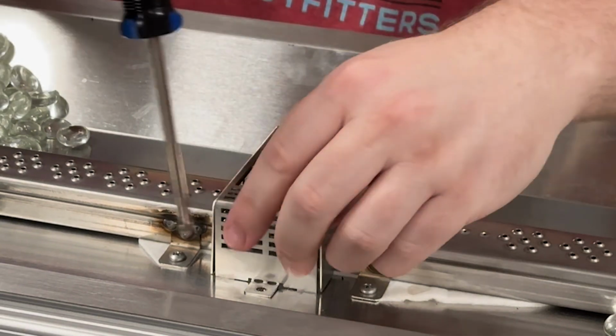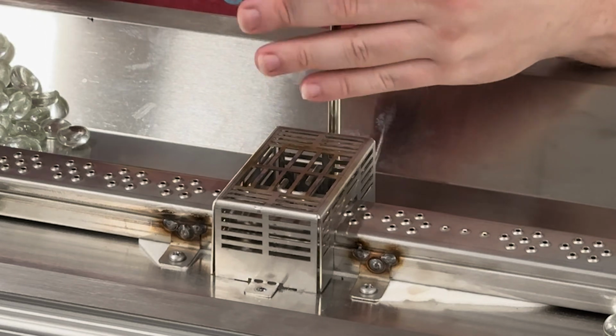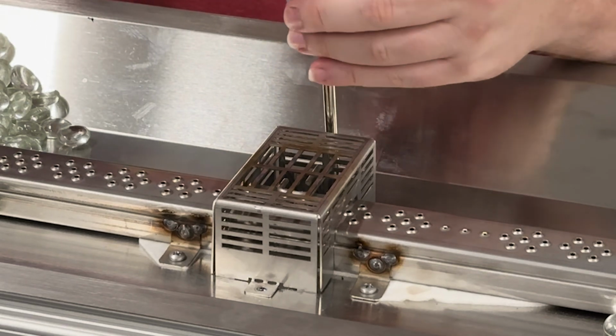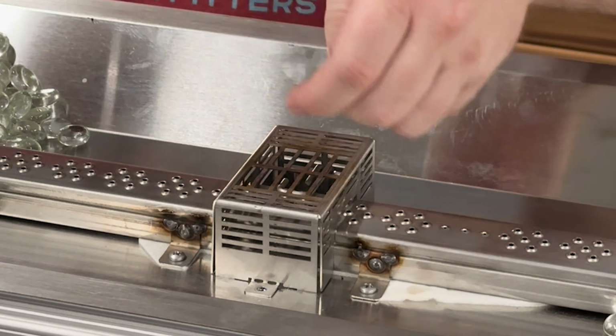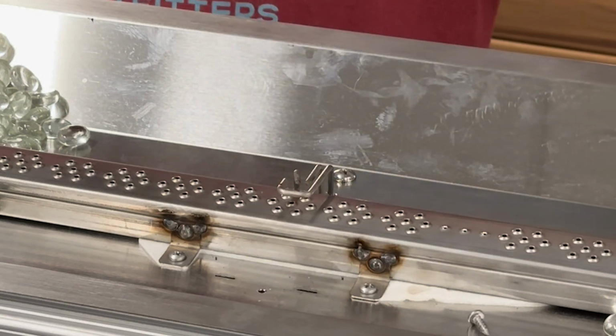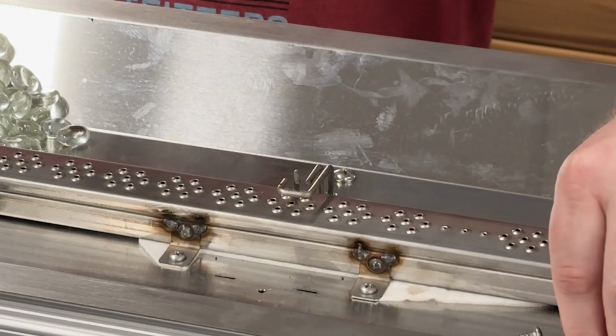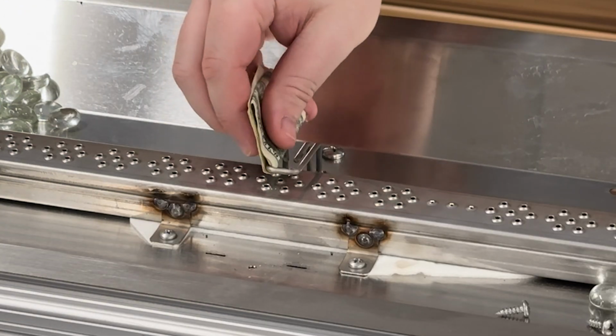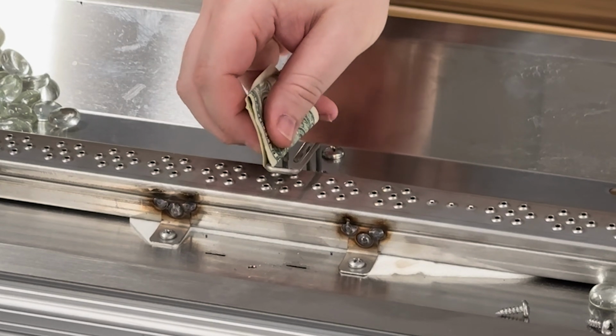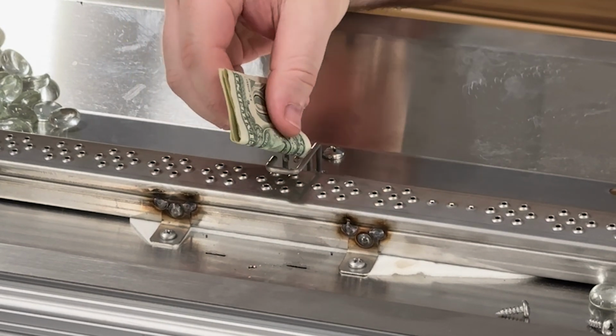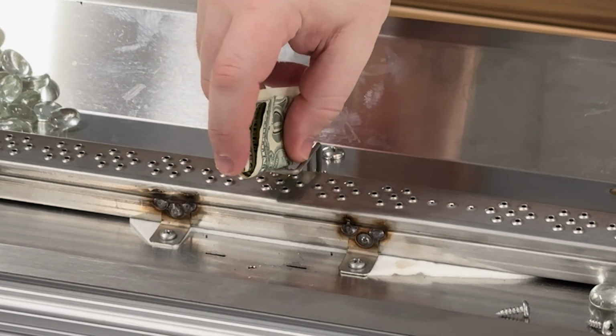To troubleshoot this issue, remove the ignition wind guard by unscrewing the two screws holding it in place. Clean off the sensor and ground rods with an emery cloth. If you don't have an emery cloth, we found that a dollar bill has a similar grit to wipe down these rods without causing any damage. Take care not to bend or twist these rods, as you could damage the ceramic housing around them.